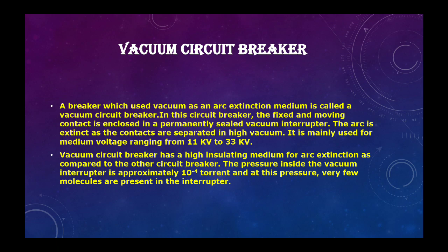Vacuum circuit breaker has a high insulating medium for arc extinction as compared to other circuit breakers. The pressure inside the vacuum interrupter is approximately 10 to the power minus 4 torr. And at this pressure, very few molecules are present in the interrupter.